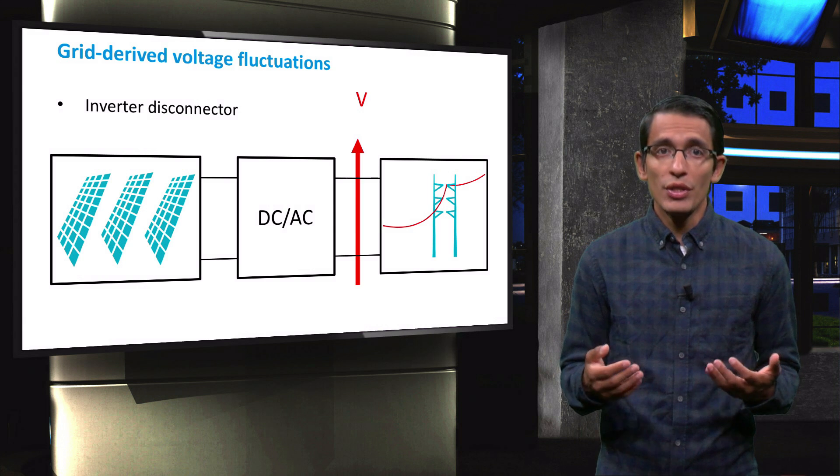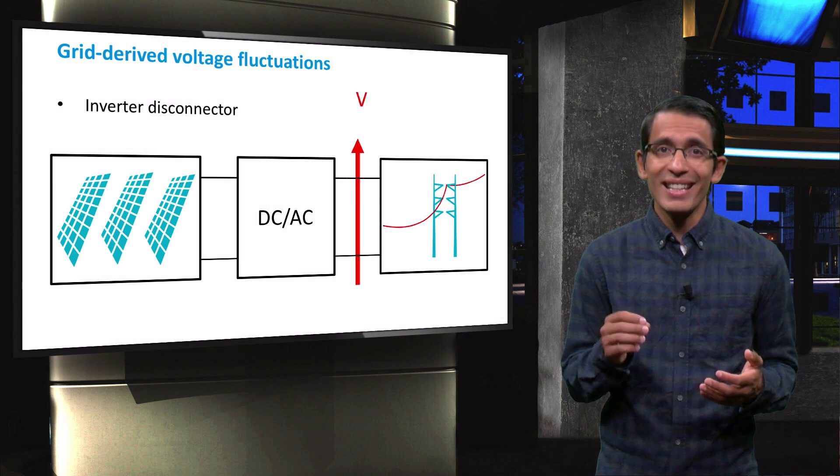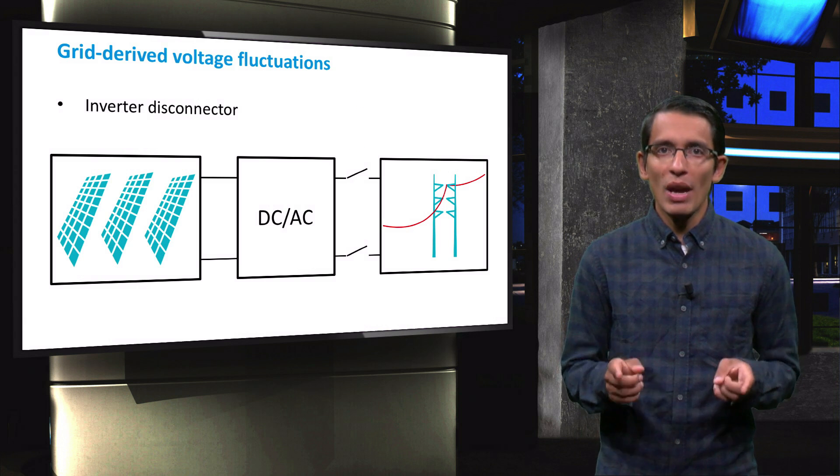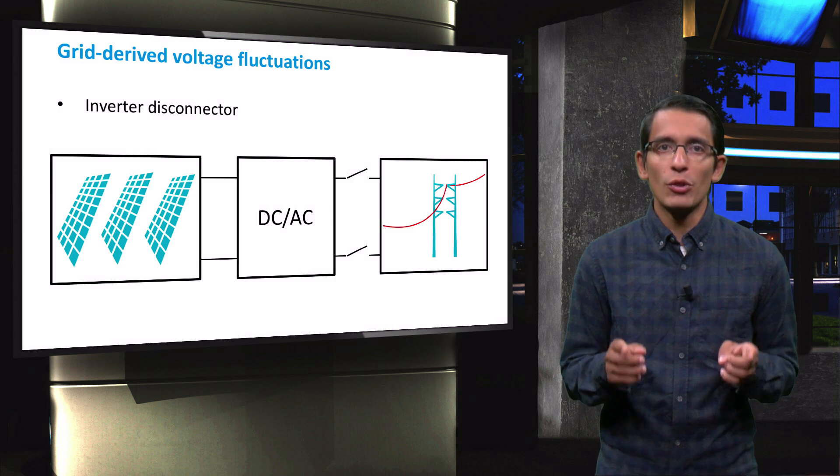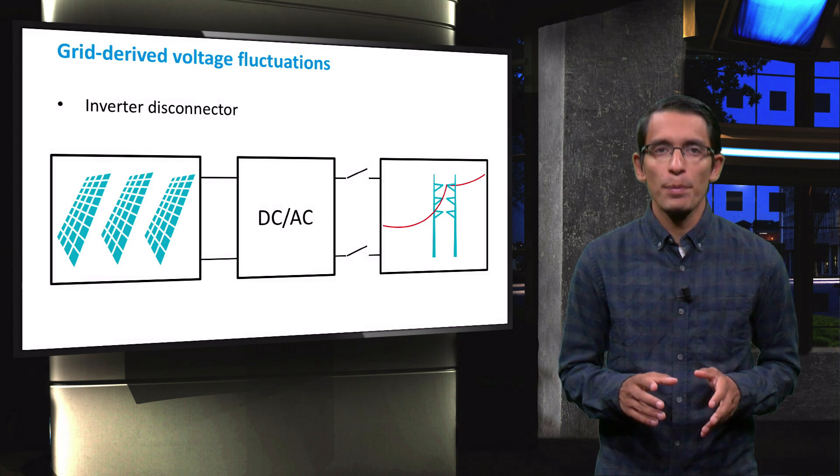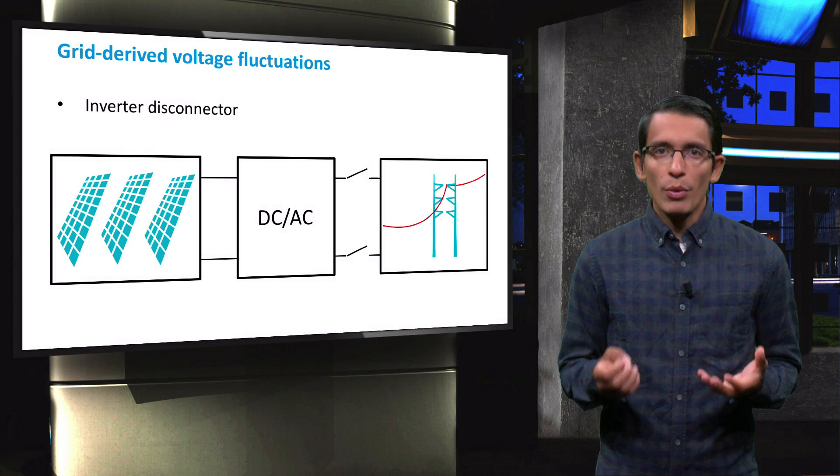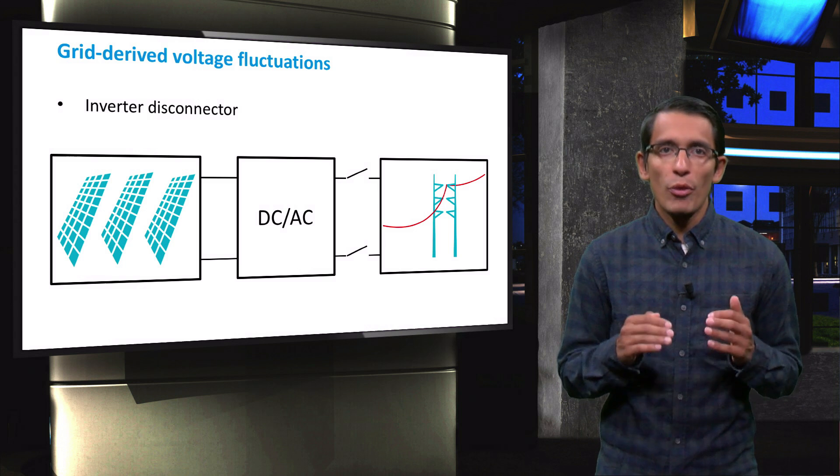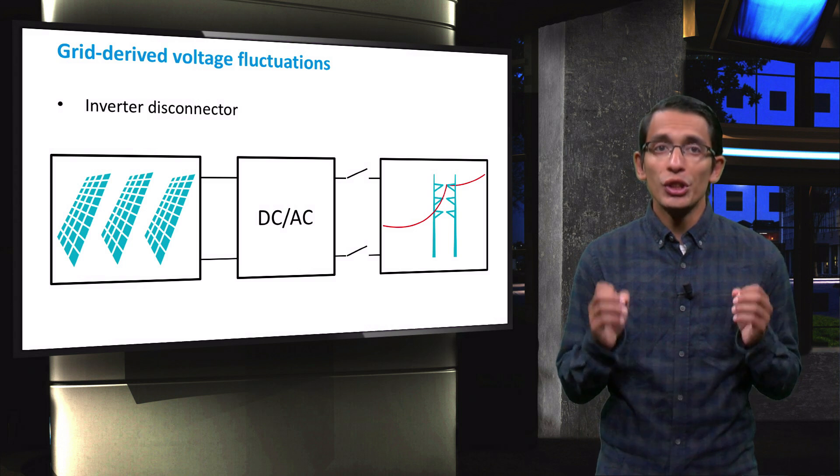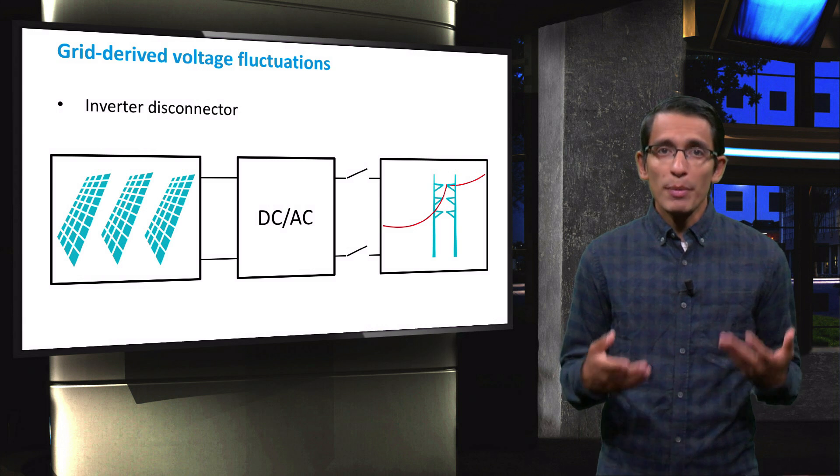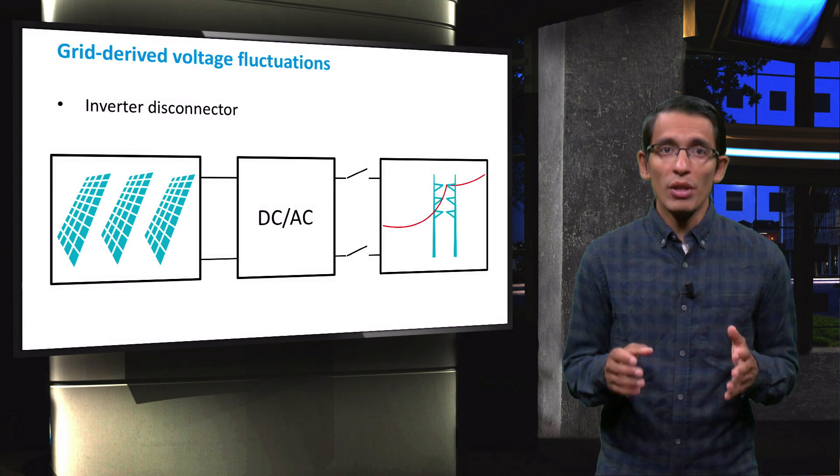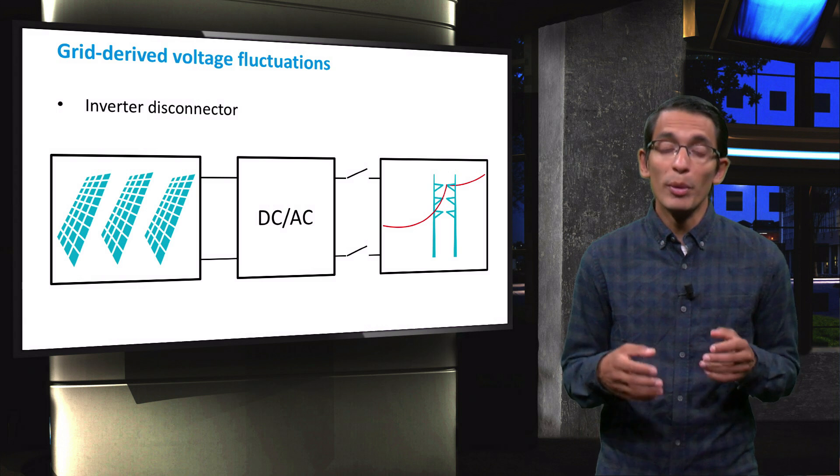In these situations, inverters normally feature a disconnecting system that is set to avoid the grid-derived voltage fluctuations that may be transmitted to the PV system. If the voltage of the grid is higher or lower than a preset threshold, the disconnector will shut off the PV system from the grid. This means that the PV power generated during this period of grid's instability will be wasted.